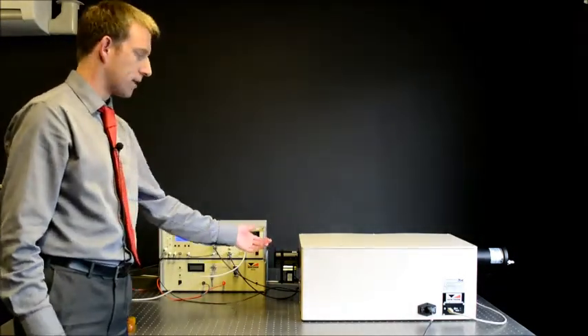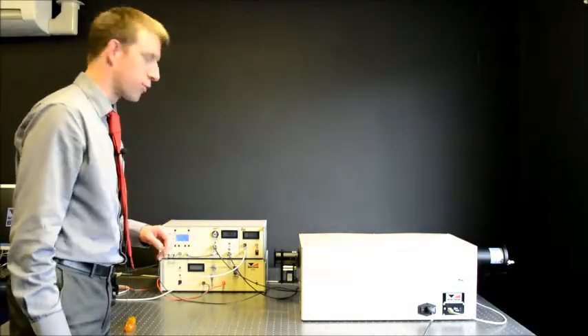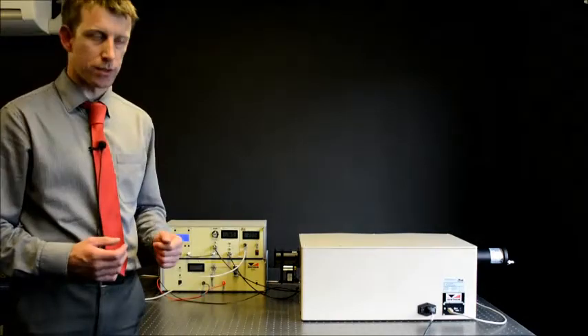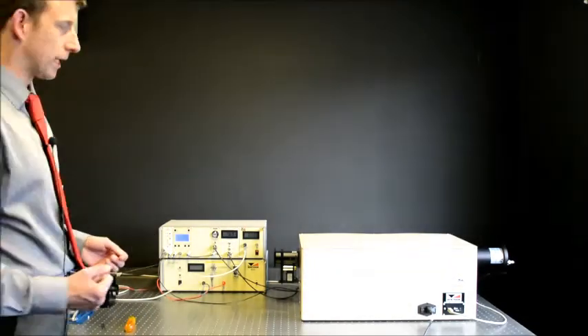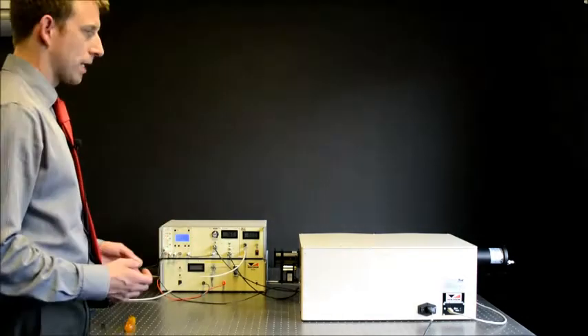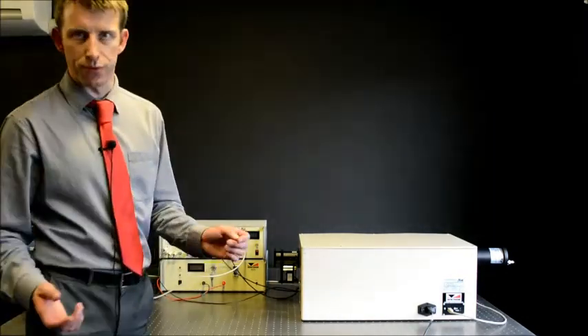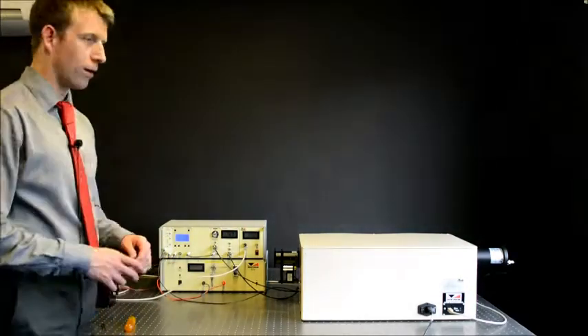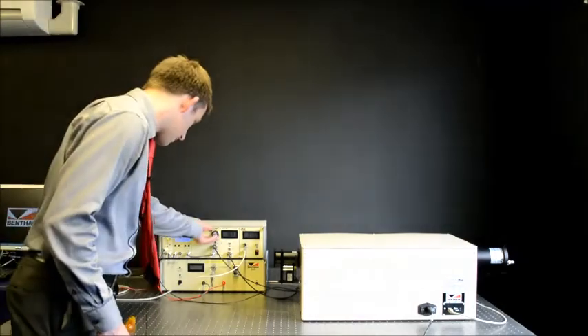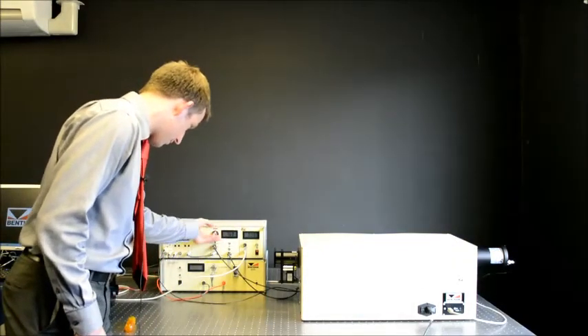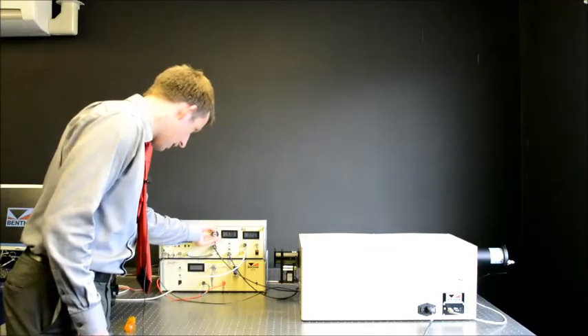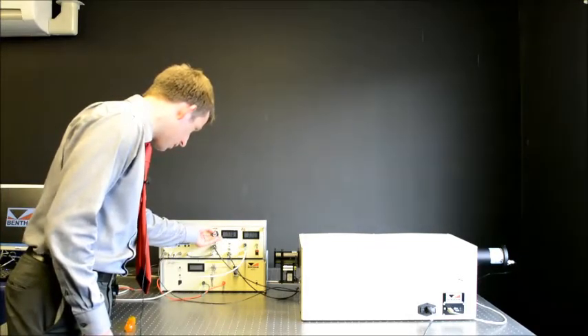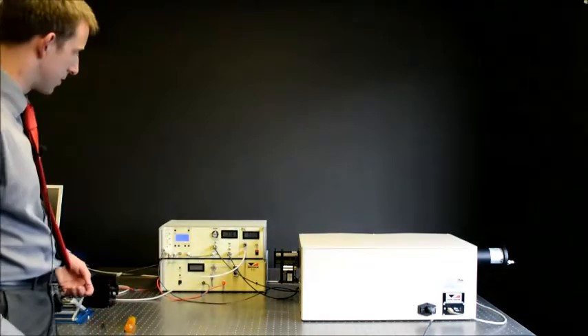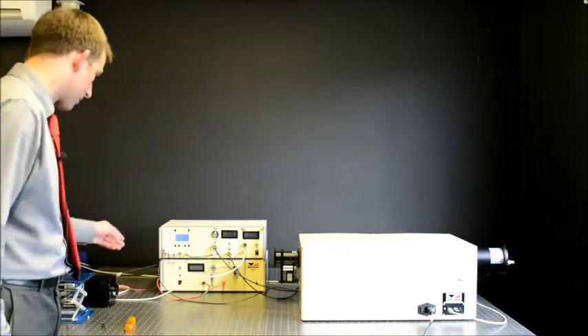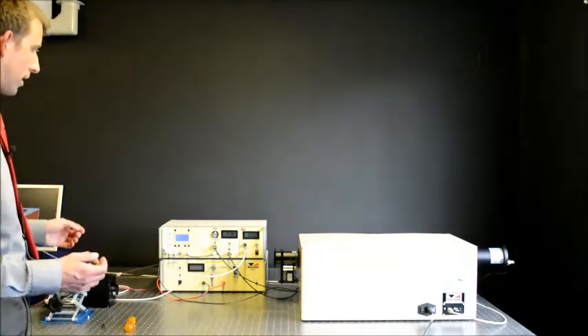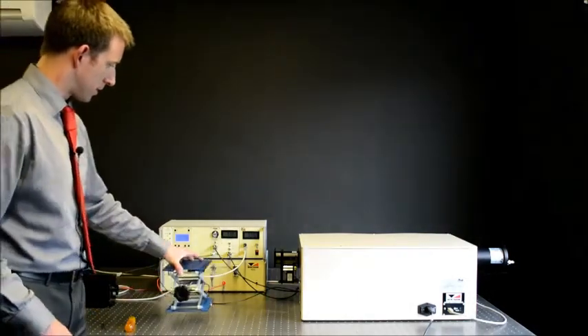We have fitted a 10-slot blade, so the dial on the 218 optical chopper, which sets the frequency, reads correct, as opposed to the use of other blades in the set provided. We tend to recommend measurements at 175 or 225 Hz, but certainly not a multiple of the mains frequency. So if I set the optical chopper to 175 Hz and lock the dial in place using the retaining tab underneath. Now we can set up the system to calibrate.